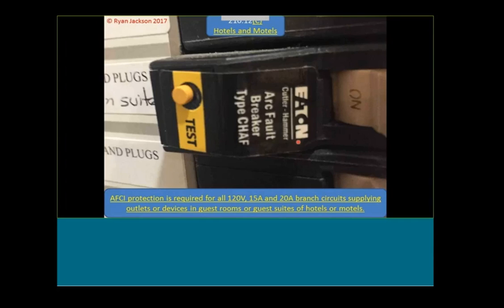Here's 210.12, which talks about AFCIs. AFCI protection is now required for all 120 volt, 15 and 20 amp branch circuits supplying outlets or devices in guest rooms or guest suites of hotels and motels. So essentially every 120 volt circuit in those rooms now requires AFCI protection — this probably wouldn't apply to an air conditioning or heater circuit, depending on voltage and current.